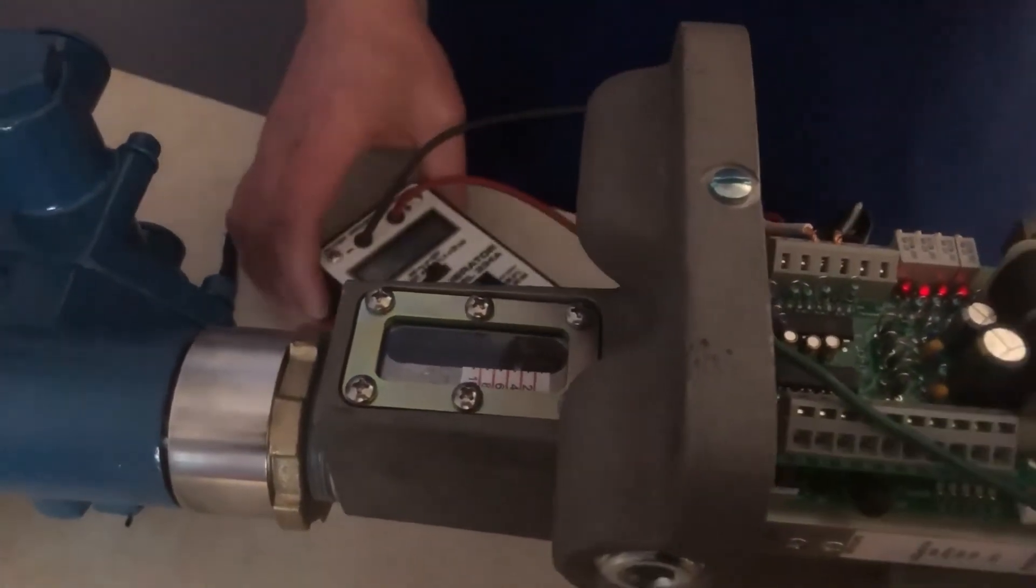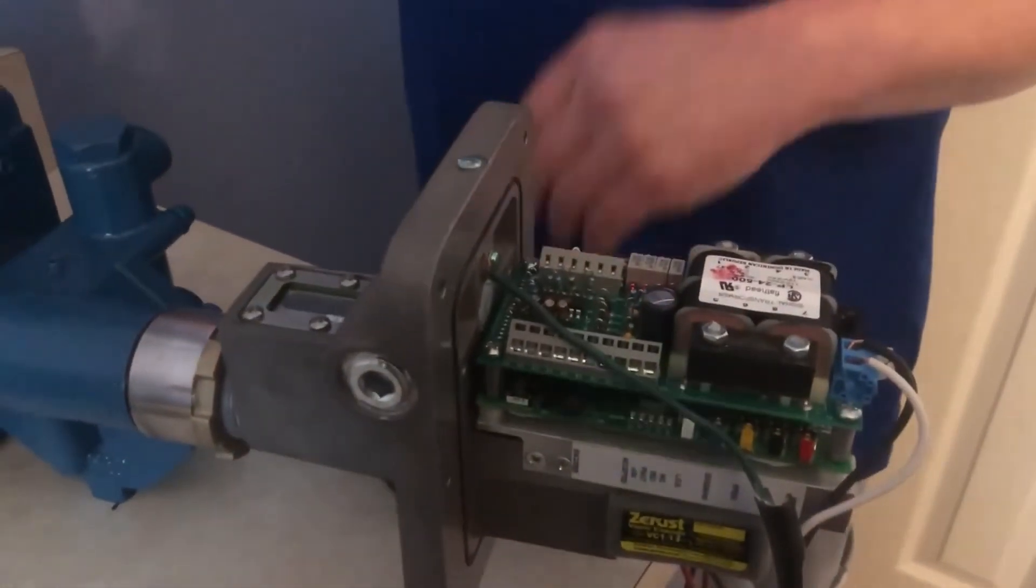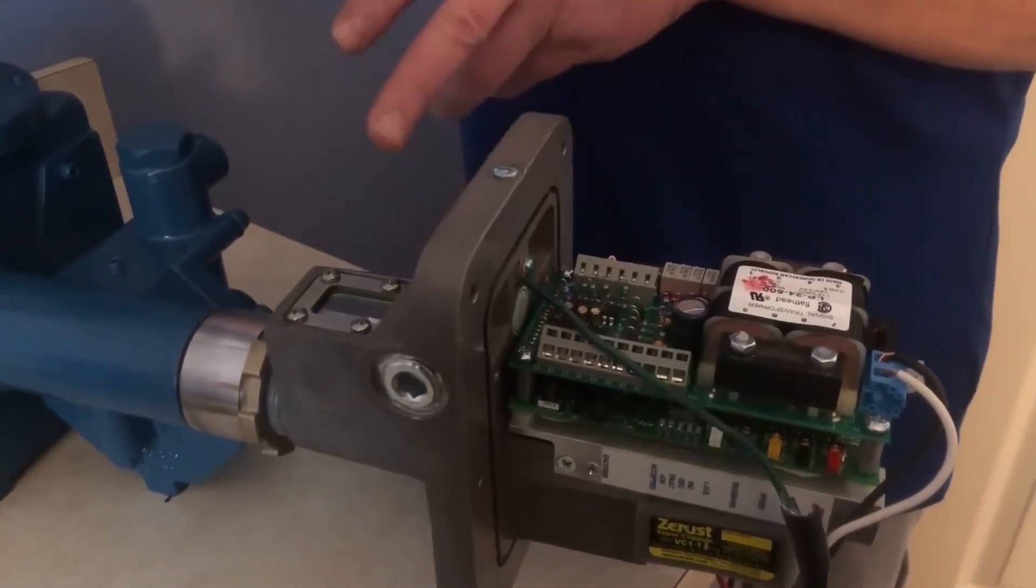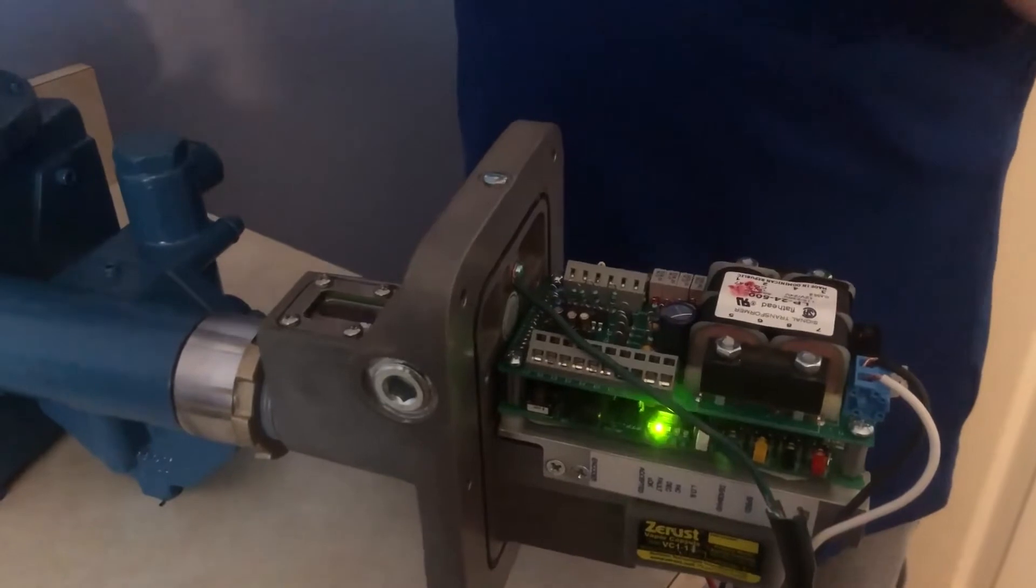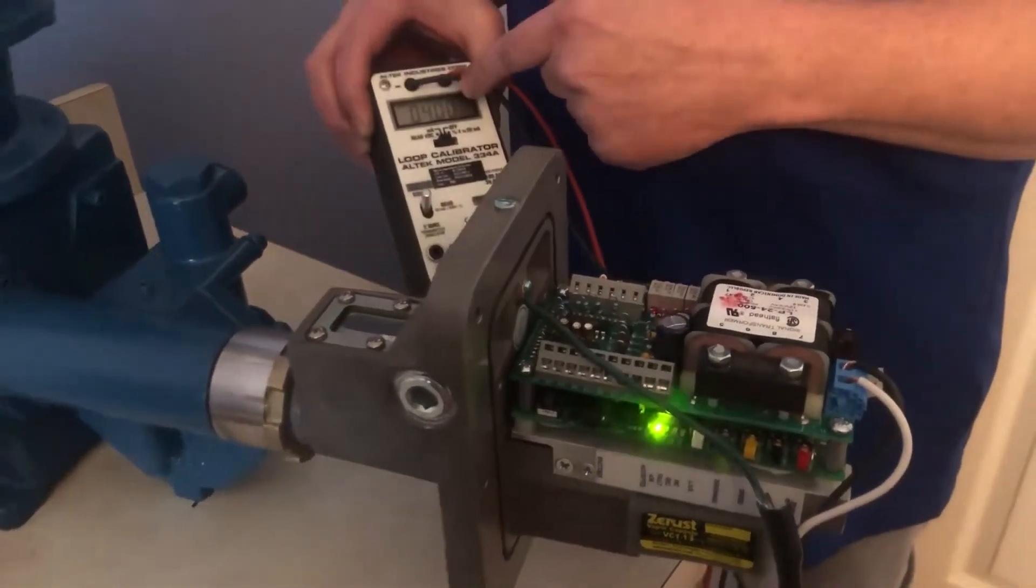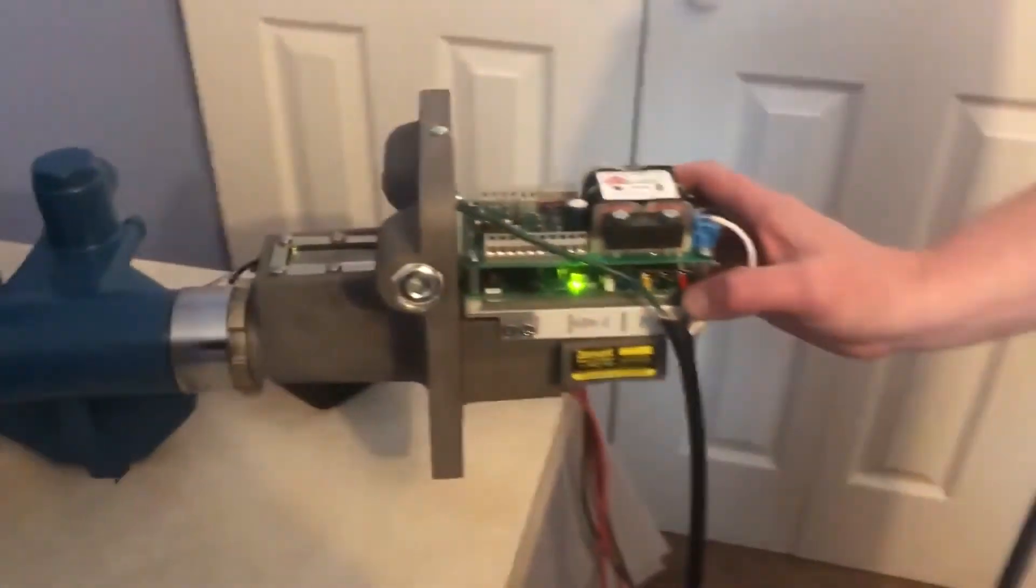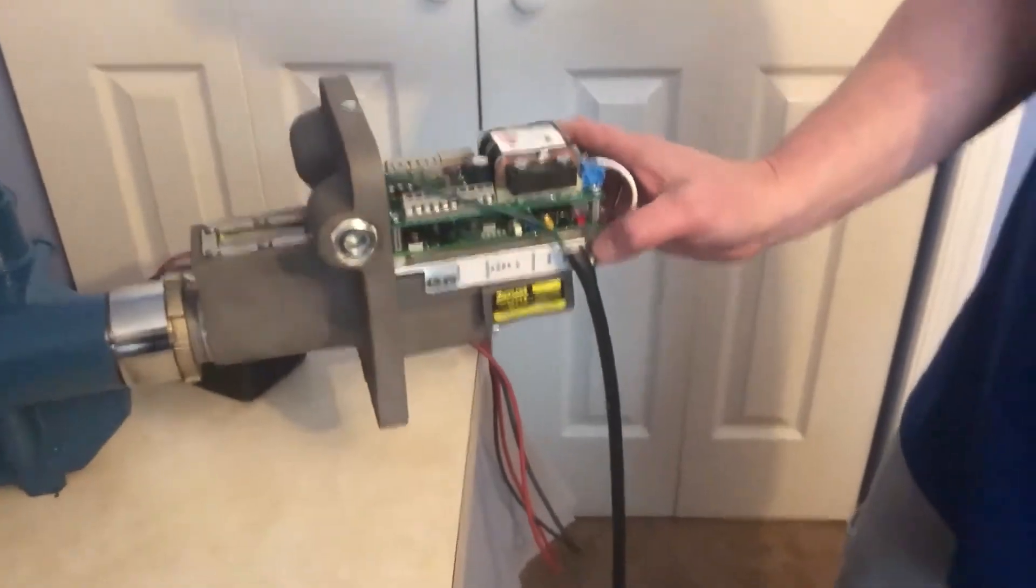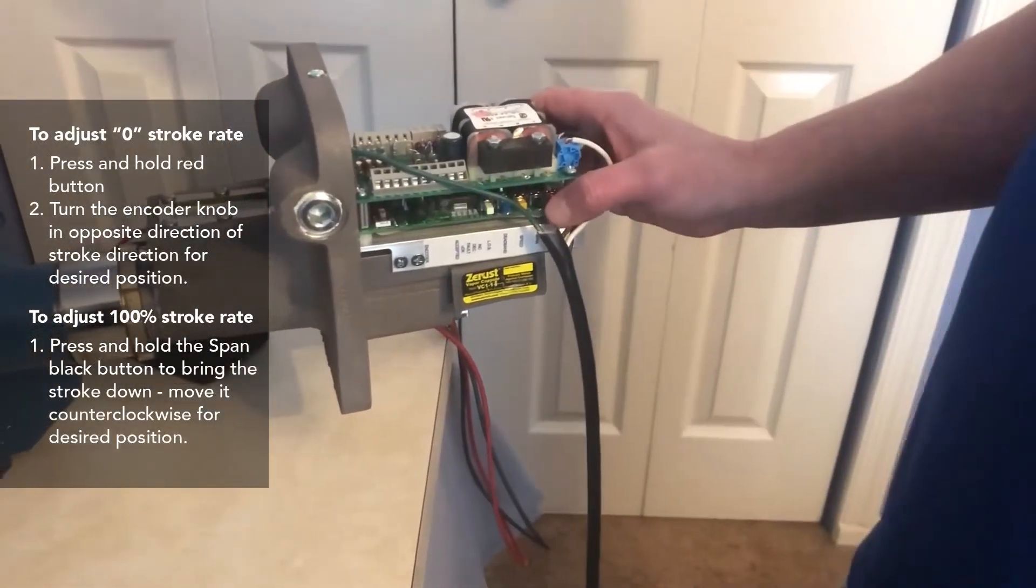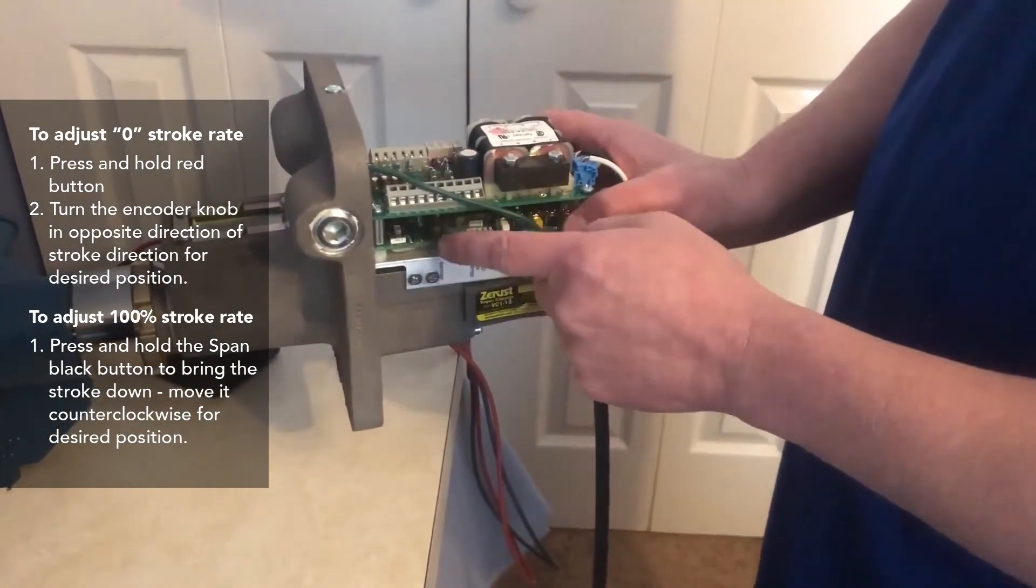Now, what we'll do is you can adjust these points. So what we're going to do is change the four milliamp zero point on the pump to another stroke setting. While four milliamps is on and into the controller, we'll come over here. You see the red button where it tells you it's zero. Press and hold. And as you turn this encoder knob, you want to go whichever way you want to go, you want to go the opposite way on the knob. So if I want to move the stroke forward, we want to turn the encoder knob clockwise.